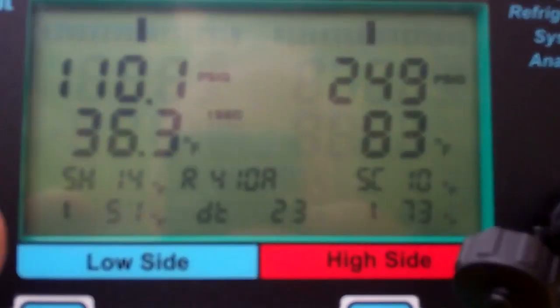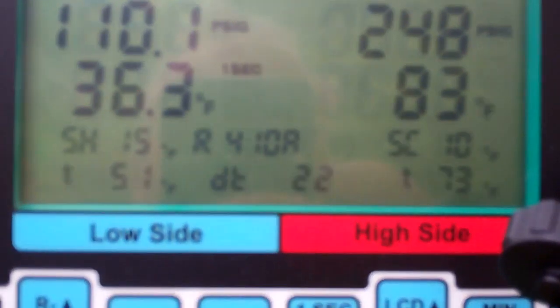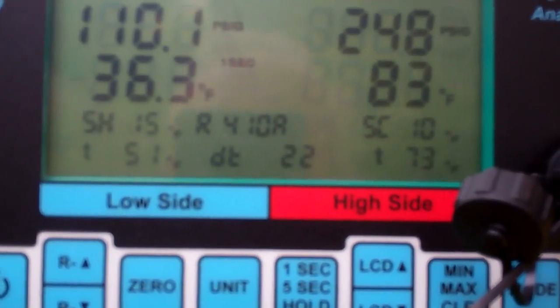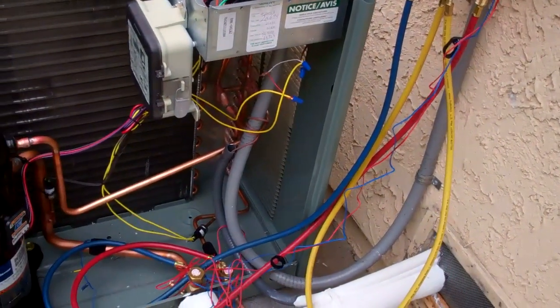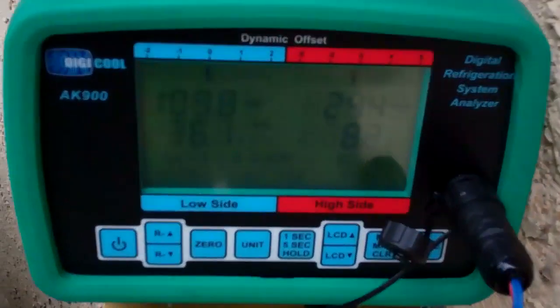Calling that good. Superheat is 14, under low load. Liquid line temperature is 73, so I'm subcooling 10 degrees. Calling it good, liking the Digicools.